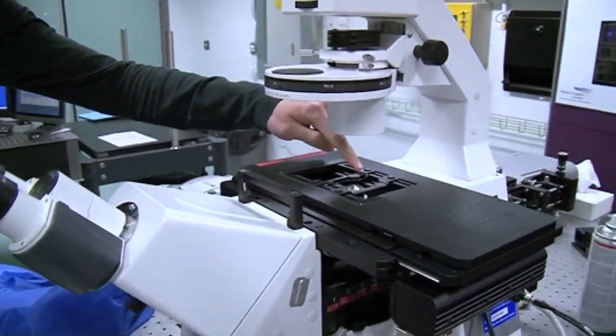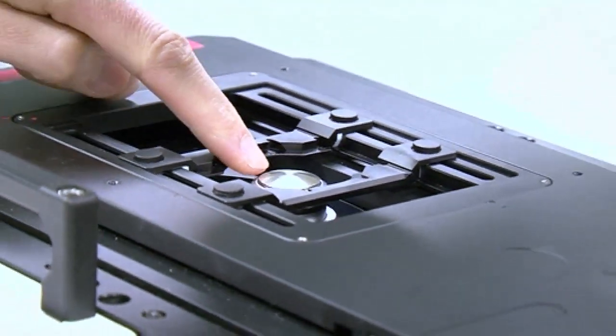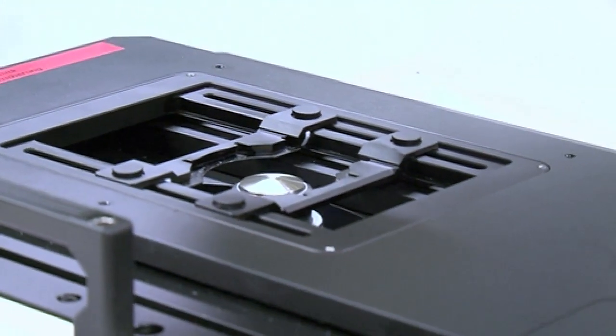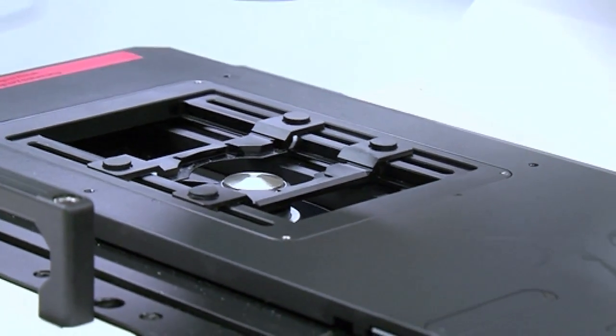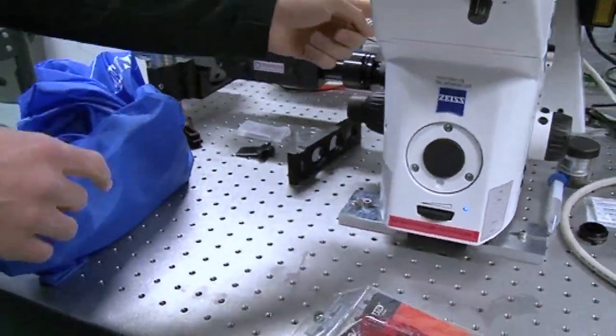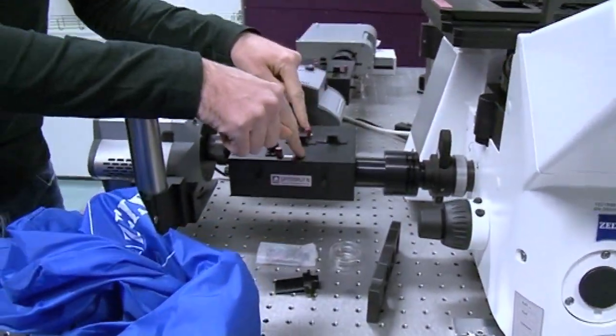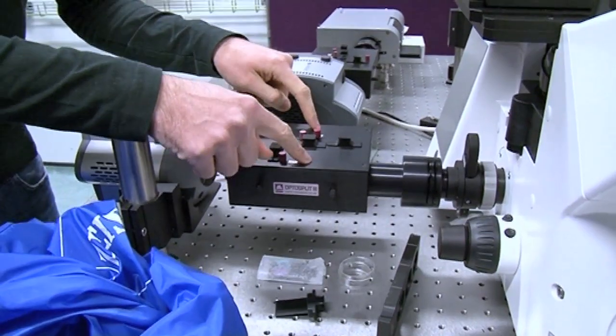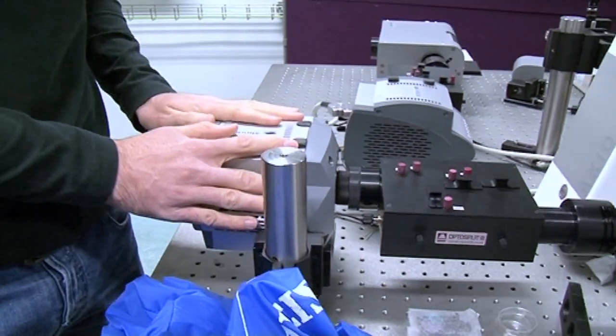So this is a typical microscope. You put your sample here and this metal colored object here is called the objective lens. And that's what does all the magnification that allows you to see really tiny things. And the laser beam comes up through the objective lens. And then the fluorescence that you produce comes back down through the objective lens. And then it comes through here. And this thing splits the fluorescence into three different colors. And they're all imaged onto the camera, which is here.